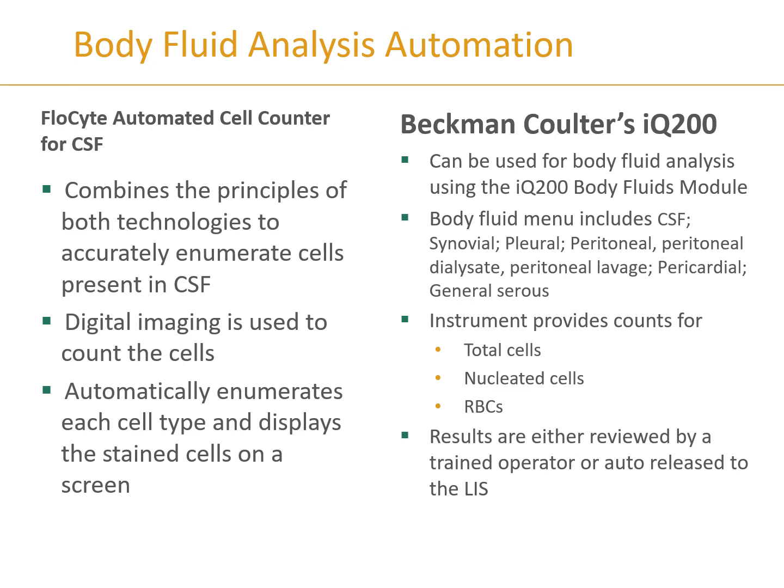Beckman Coulter can be used for body fluid analysis and has been approved for CSF, synovial, pleural, peritoneal, peritoneal dialysate, peritoneal lavage, pericardial, and serous fluid — a wide range of capabilities. The instrument provides total counts and nucleated cells including white blood cells, epithelial cells, and any nucleated elements, as well as red blood cell counts. The operator can review the cells and counts, or it can be set up to automatically auto-verify results to the LIS.